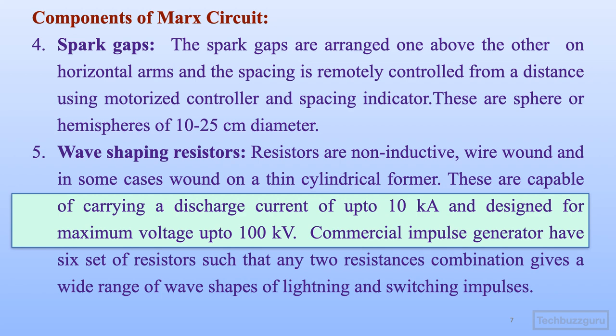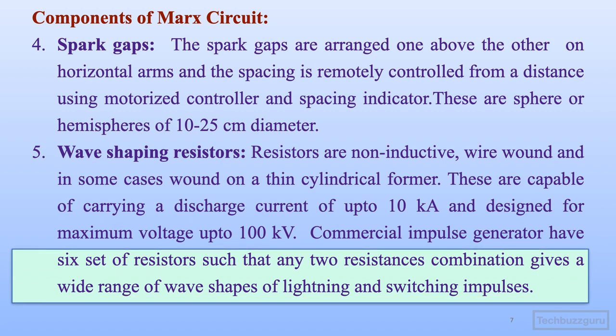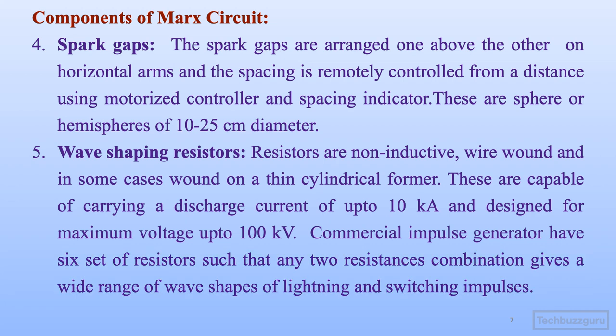Commercial impulse generators have six sets of resistors such that any two-resistor combination gives a wide range of wave shapes of lightning and switching impulses. Impulse voltages are basically of two types: lightning impulse voltages and switching impulse voltages. The same circuit can be used for generating either type of pulse by using a set of resistors instead of only two resistors R1 and R2.